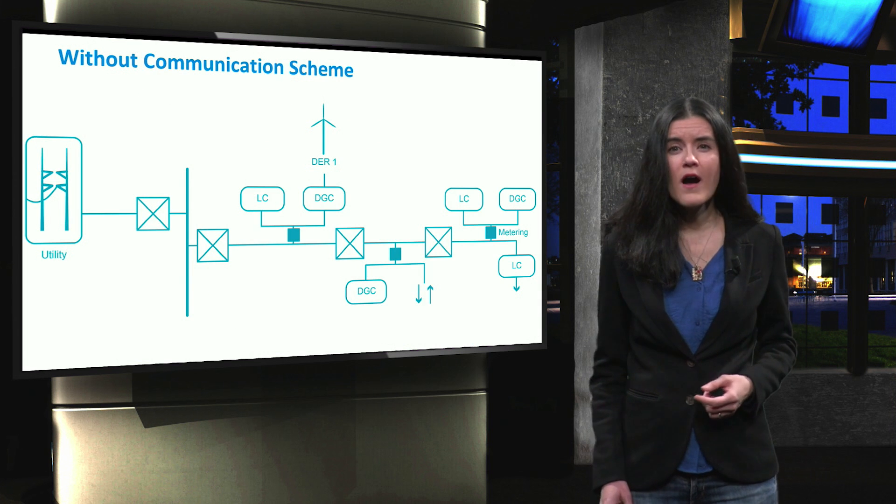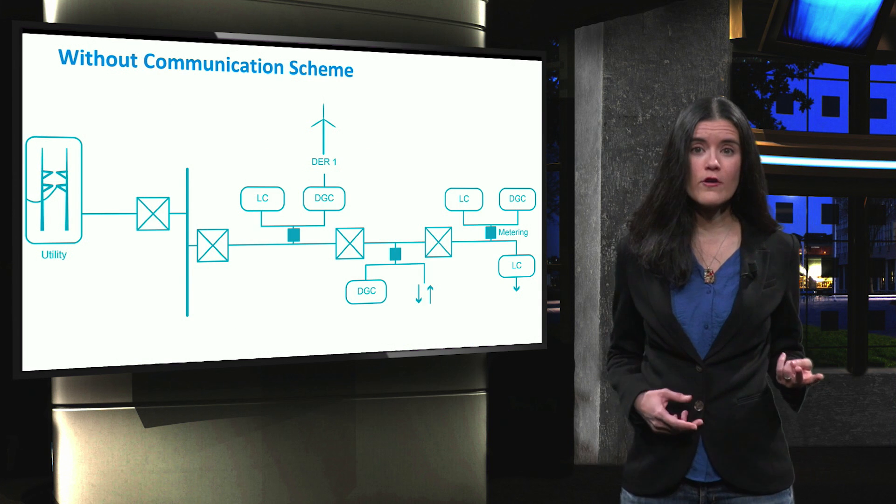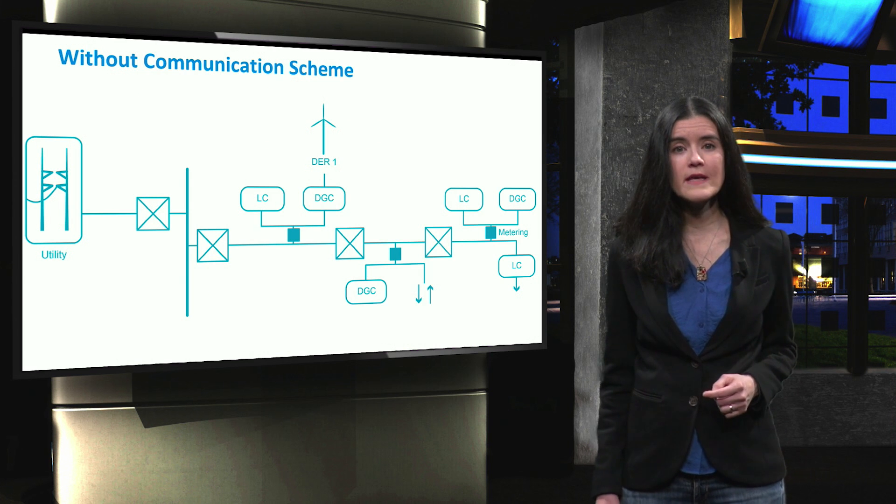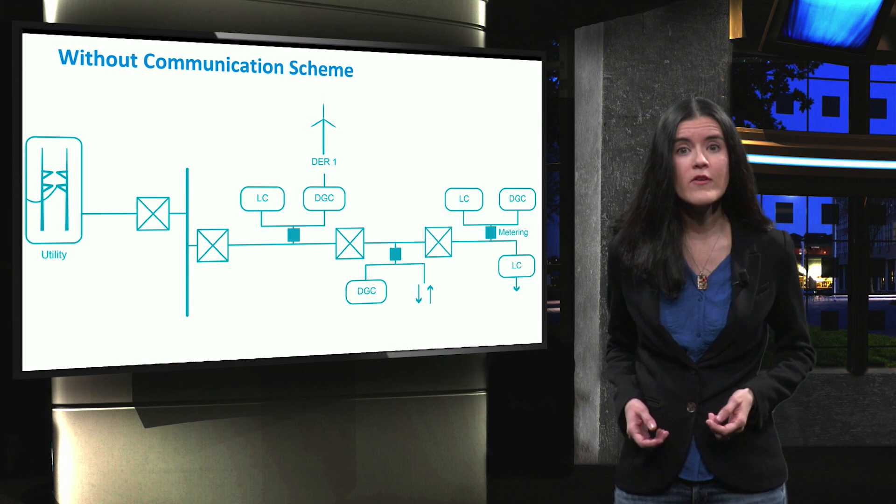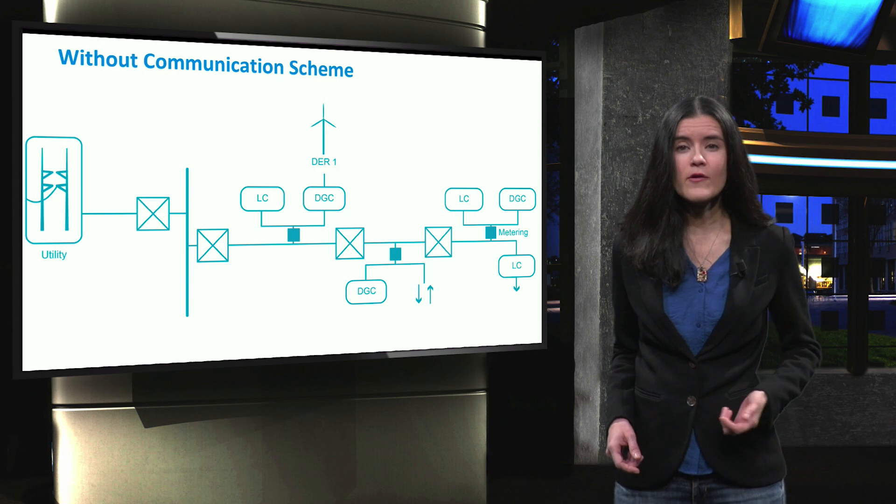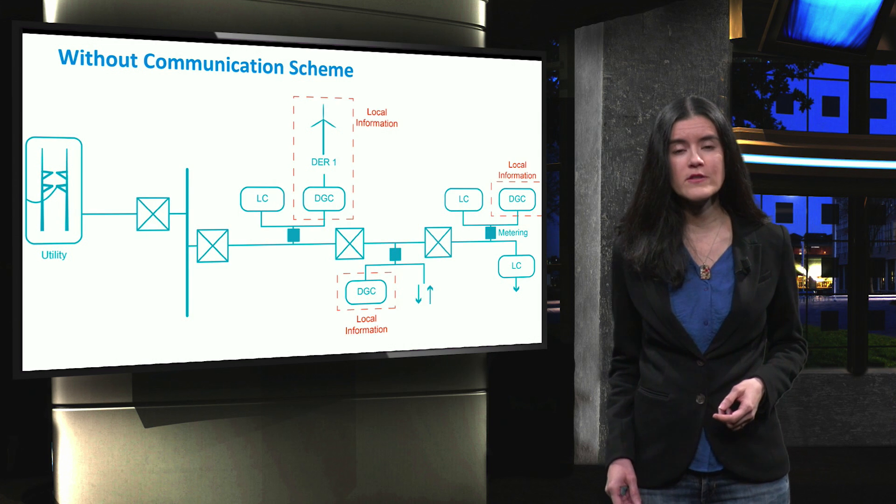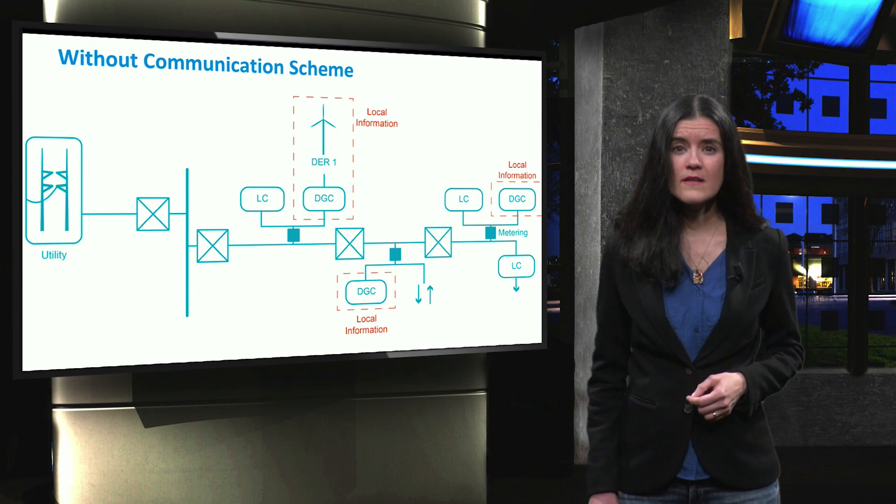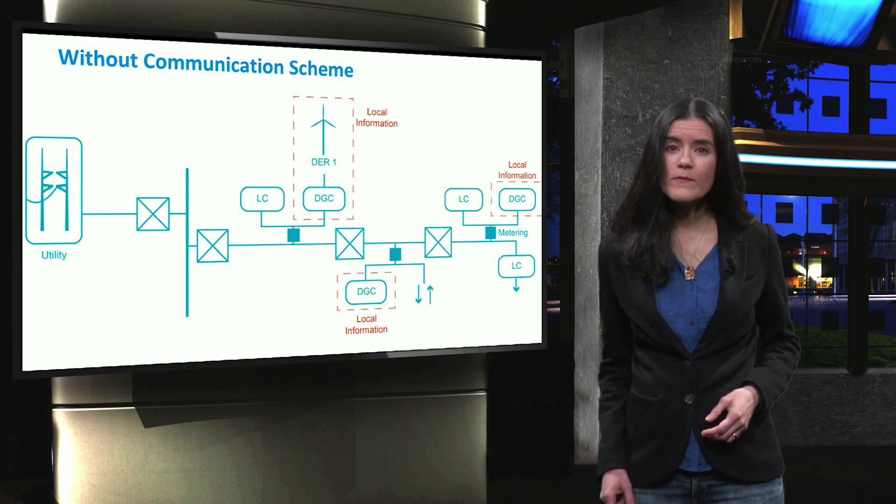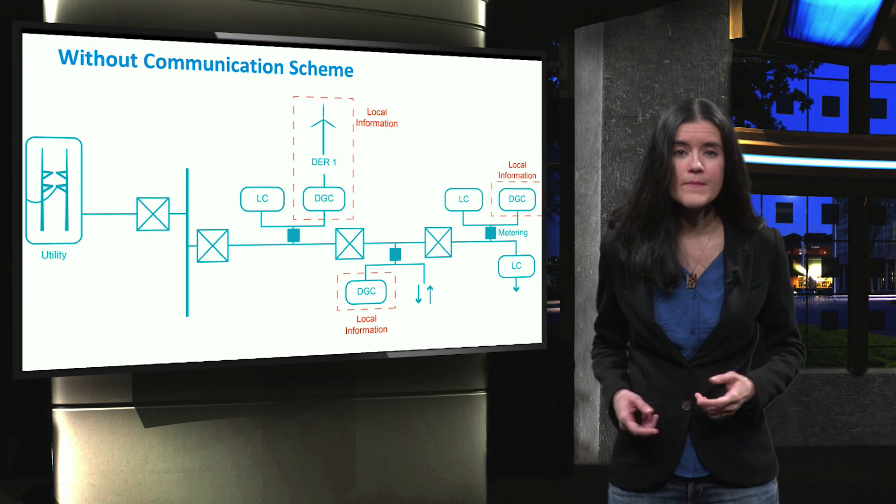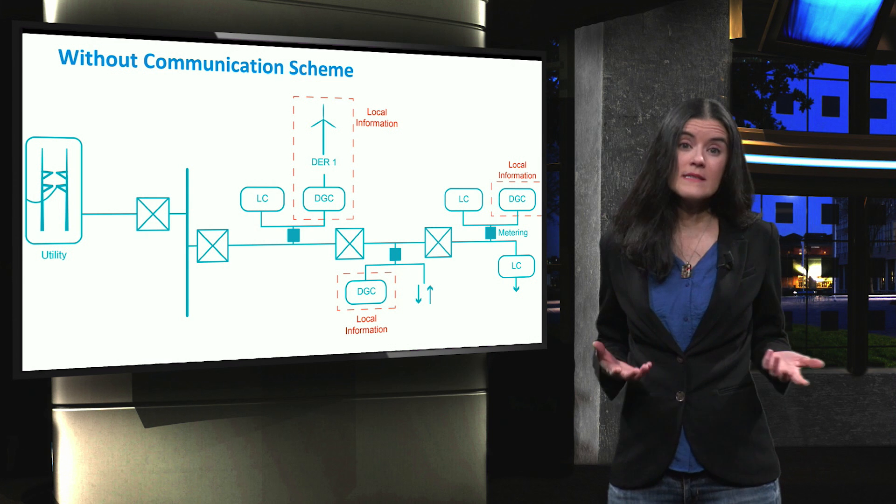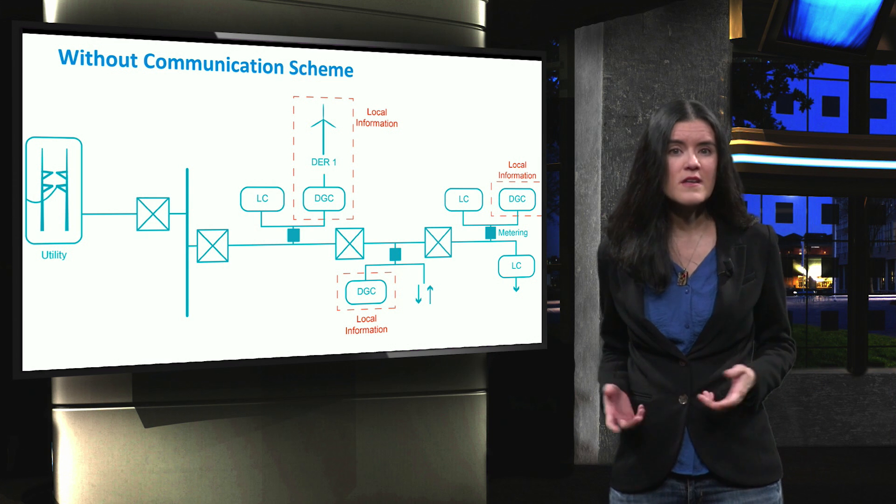Protection schemes are generally divided into two groups, with and without communication. In the no-communication scheme, the time-current tripping curve of the relays in the microgrid is set based on the local information. The selectivity in the scheme is low, since the decisions are based on local information instead of the whole microgrid. The advantage of such protection scheme is the lower cost, as the computational and ICT costs are not in place.